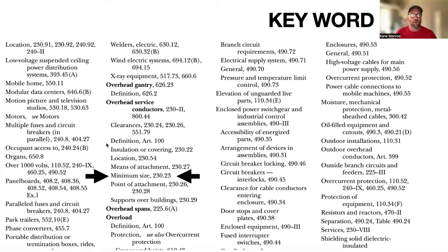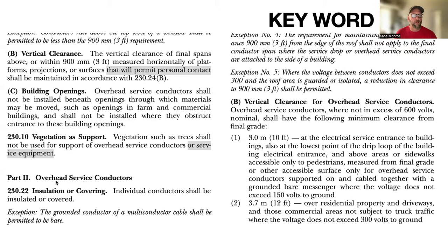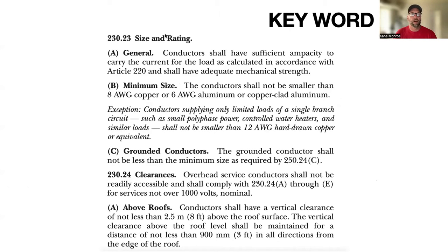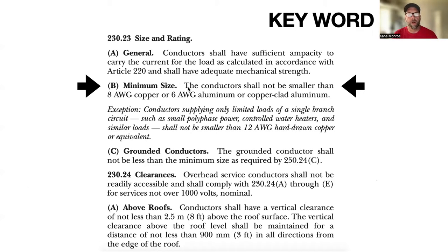Now we take that and go to Article 230, Part 2 — that's the overhead service conductors, which is what was asked in our question. We go to 230.23, 'Size and Rating' — that's what the index directed us to. And then we look down and 230.23(B) is 'Minimum Size,' which reads: the conductor shall not be smaller than 8 AWG copper, or 6 AWG aluminum or copper-clad aluminum. Keep in mind that when testing, everything is usually copper unless stated as aluminum. Also note there are exceptions listed — some questions will have answers pulled from the exceptions.